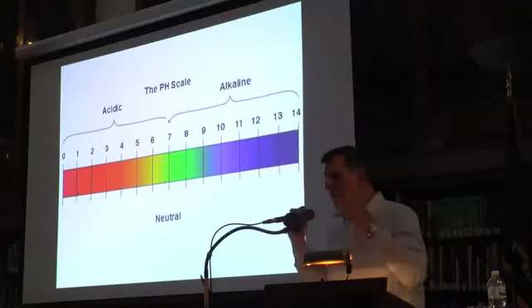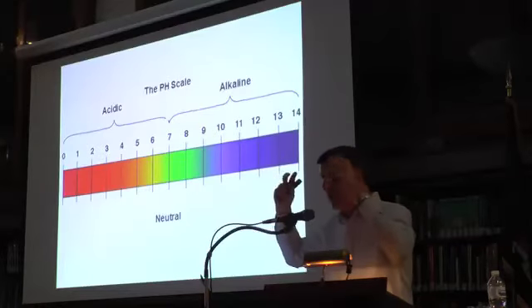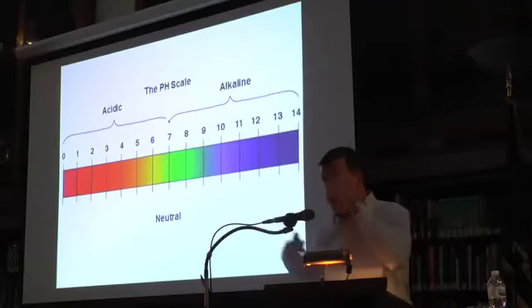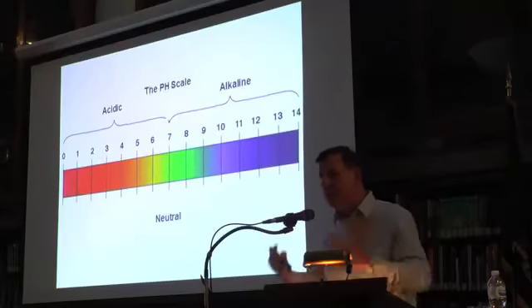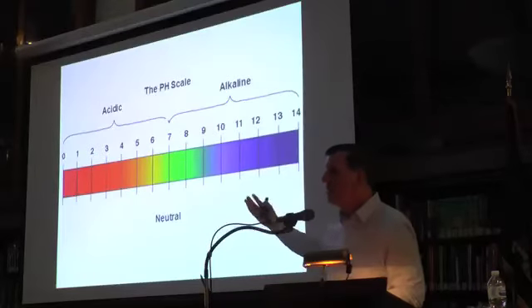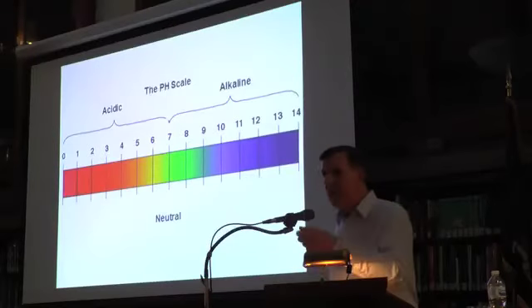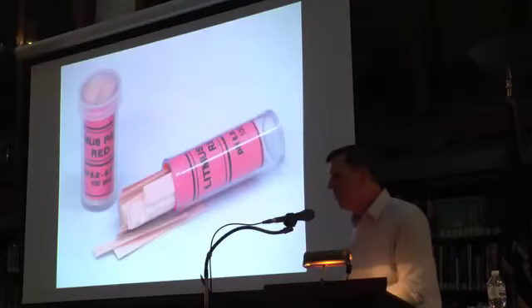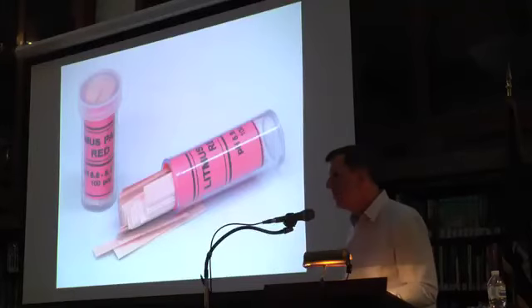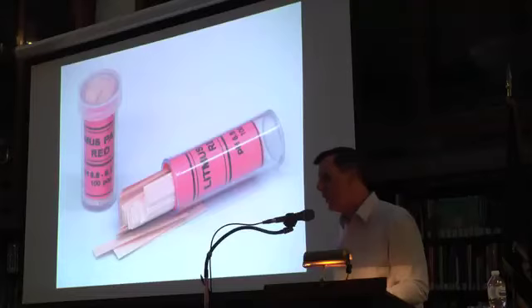And it's very, very difficult for the steam to bust through those bubbles because the liquid water in the bubbles is condensing the steam, and also that carries off into the building. So you get this priming, surging, all these bad problems that happen if the pH is too high, and that's why they use the vinegar to move it this way and the baking soda to move it that way. So when you're blowing down a boiler, get yourself some litmus paper or a pH meter, because it's fancy now. We've got electronic things that do this, and just check the pH. Ideally, it should be somewhere between 7 and 9 for steam heating.